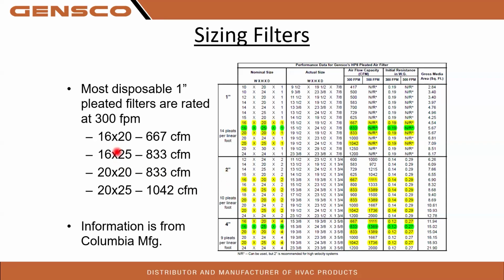2 inch, well, you can see 20x20 is only 833. 2 inch, 20x20x2, now at 500 feet per minute, which is what we're rated at, 1389. So can we use a 20x20x2 on a 4-ton unit that requires 1600 CFM? No. So I look at that quite a bit. There's a 20x20x4, still only rated for 1389, but your pressure drop in surface area got better. I'm sorry, this is the surface area. Again, another side that shows the pressure drop right here. So that is our surface area. 4-inch filters have more surface area, so it's less restrictive.